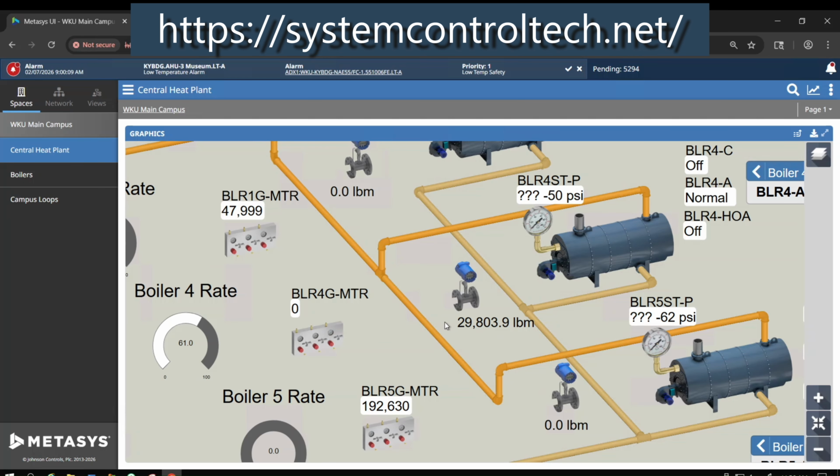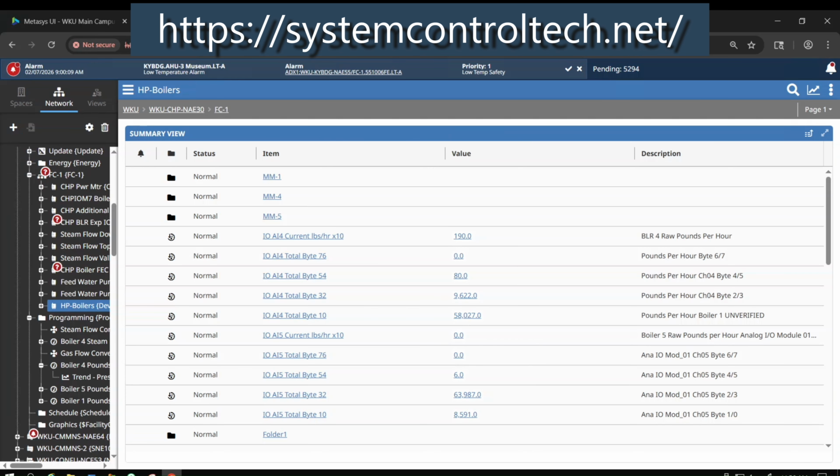The way we got that number is we took that analog Modbus signal. That analog Modbus signal was being spanned from 0 to 4,000. The way that I know that is simply because that is what the manufacturer told me. The equipment manufacturer told me, this Modbus register, this is your span value. They made the equipment, so obviously they know what they set it up to do.